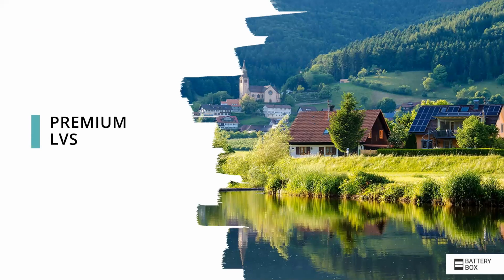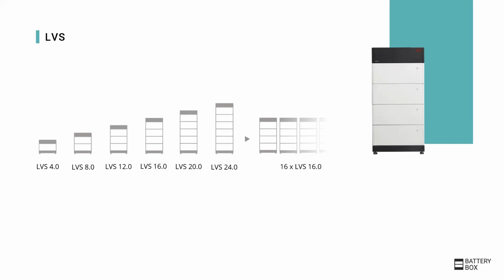After the LVL, the last premium product we will look at is the Battery Box Premium LVS. The modular concept is similar to the HVS-HVM. However, here the modules are connected in parallel, so the voltage stays at about 50 volt regardless of the module quantity. One module has 4 kWh capacity, and up to 6 modules, so 24 kWh, can be stacked in one tower. Up to 16 LVS with a maximum of 4 modules per tower can be connected in parallel to achieve a maximum capacity of 256 kWh.